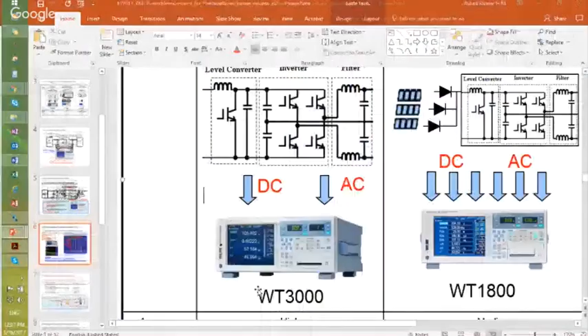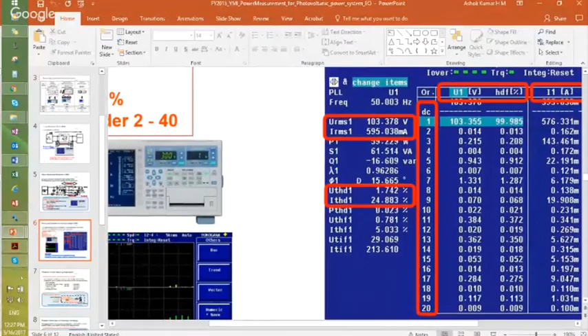If you see the power quality evaluation of an AC output in the photovoltaic industry, I think it's not visible here, I'll just zoom it. This is one of the screenshots in the power analyzer. It is measuring the voltage of channel 1, around 103 volts, and current of around 600 milliamps. And this is the table of harmonic contents, first, second, third, fourth, like that. This is the voltage harmonics and this is the current harmonics. The first one is the fundamental frequency, and then the second harmonic, third harmonic, fourth harmonic.